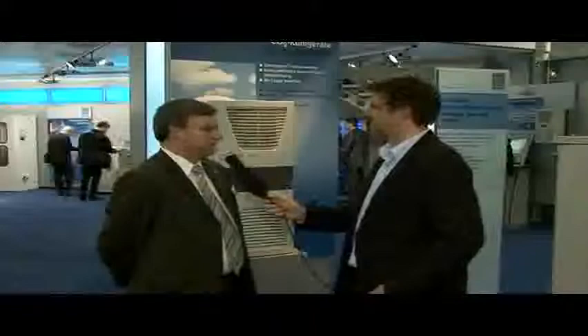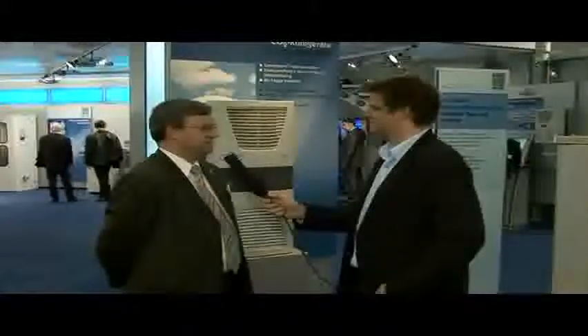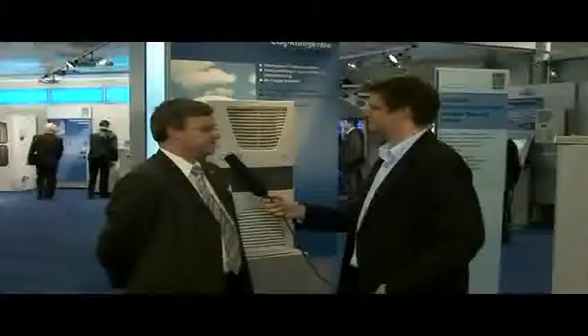What are a few years? We know Rittal is a trendsetter. How long do you need to get a unit like this to the market-ready stage? We started four years ago, made the initial test prototypes, and now have a unit that is almost ready for series production. This means we will be in a position to start delivering units to our customers shortly. What were the biggest challenges during these four years? On the one hand, the much higher pressure than in today's refrigerant circuits — we're talking 130 bar instead of 28 bar — and the changed thermodynamic flow. Instead of a condenser, we now have a gas cooler.